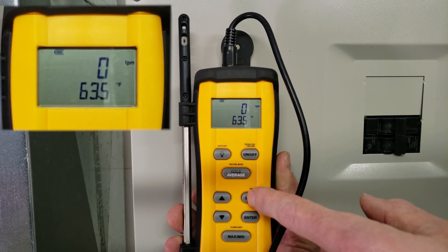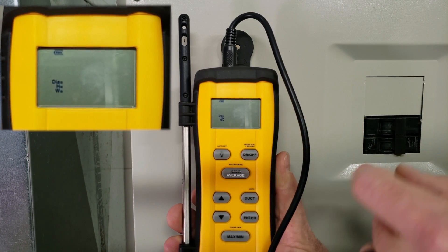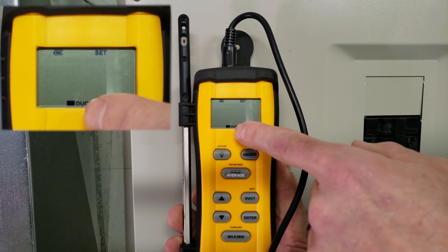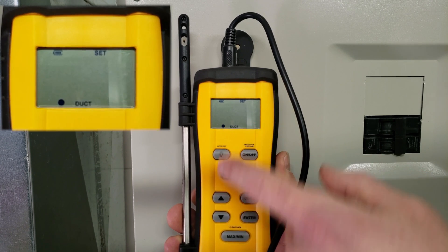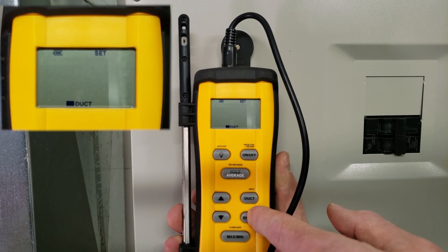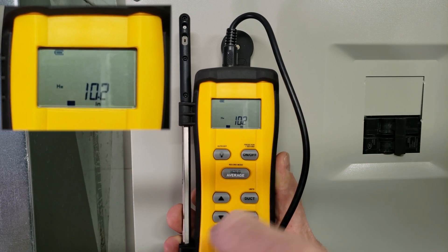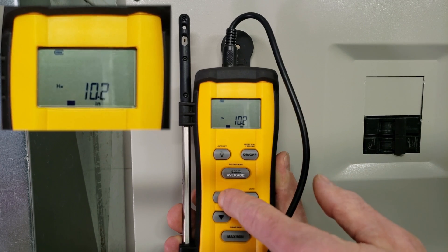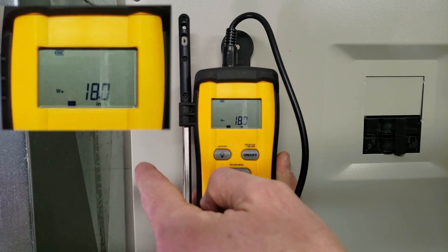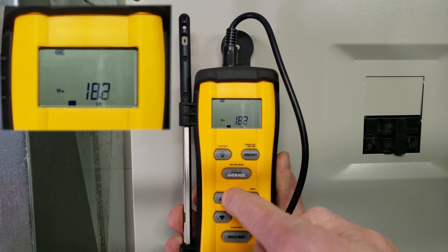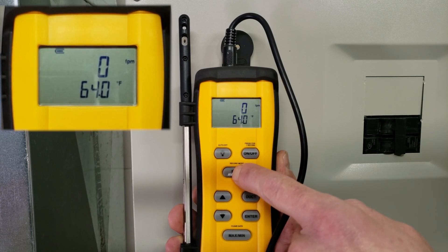We're putting this into a rectangular duct, so we press the duct button. It shows diameter, height, and width. We press enter for rectangular duct. Our duct dimensions are 10 and a quarter inches, so we'll set it to 10.2. The depth is 18 inches, so we press enter. Now we press the average button for a timed average.